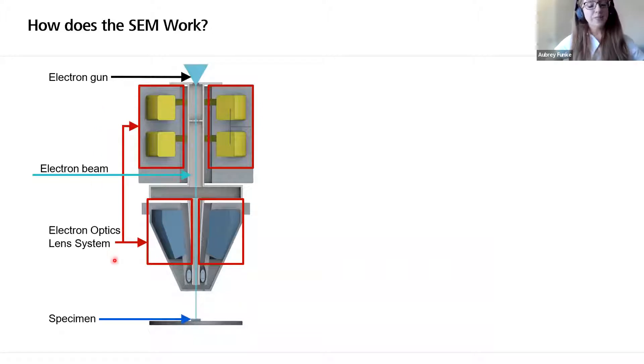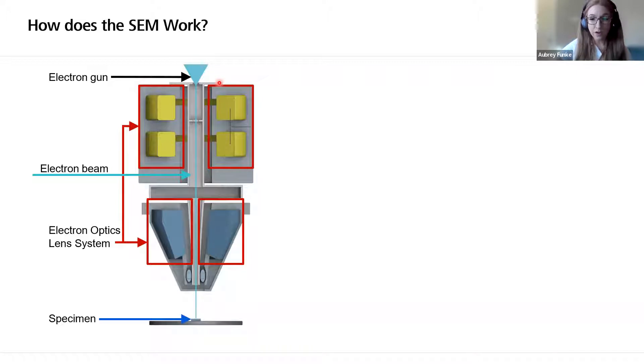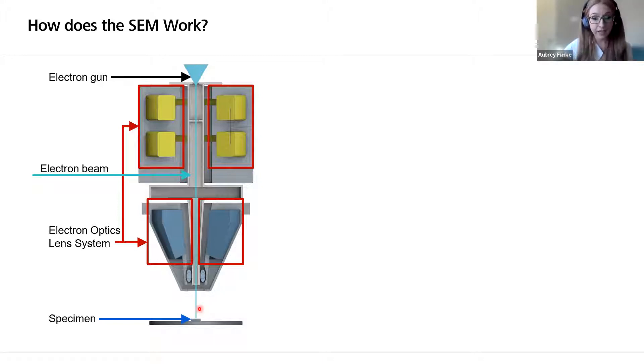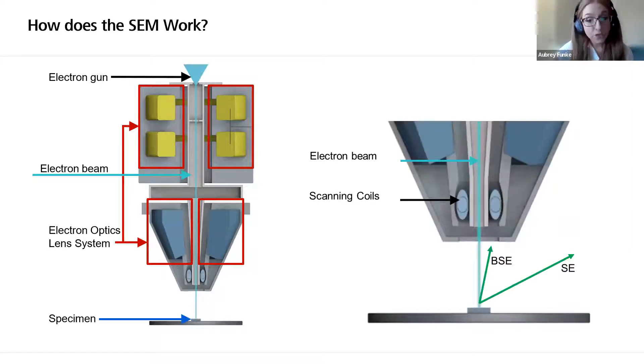This is a cartoon rendering of a cross-section of the column where the electron gun and the lenses are housed. The specimen is seated just below the final lens within the specimen chamber on the stage. Electrons are generated by the gun and accelerated by a voltage of anywhere from 0.1 to maybe 30 kV through the electromagnetic lenses, which form and focus the beam and guide it onto the sample. The electron beam is then rastered across the sample using scanning coils, releasing signals such as secondary and backscattered electrons.